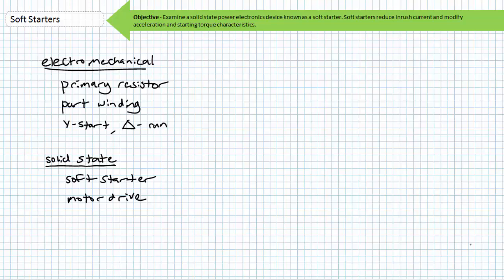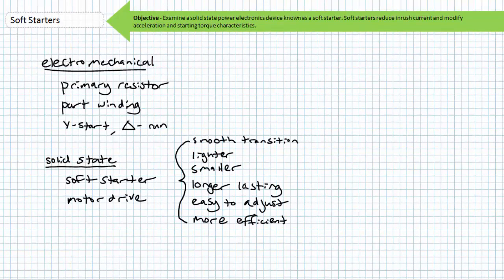Really, the only time we ever saw an attempt to stage the transition between start and run mode is using a primary resistor reduced voltage starter with two banks of primary resistors. Even so, this is still a stepped approach, and the graph of inrush current would show noticeable disjoints during the transition periods. Doubly so for Y-start delta run reduced voltage starter, since this is an open transition method in which the motor windings are briefly de-energized between start and run mode. The open transition would be characterized by an undesirable transient spike. For this reason, soft starters are employed.